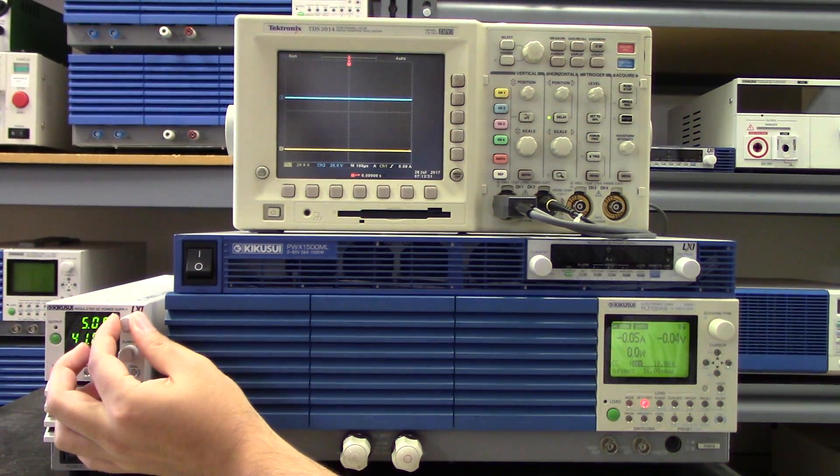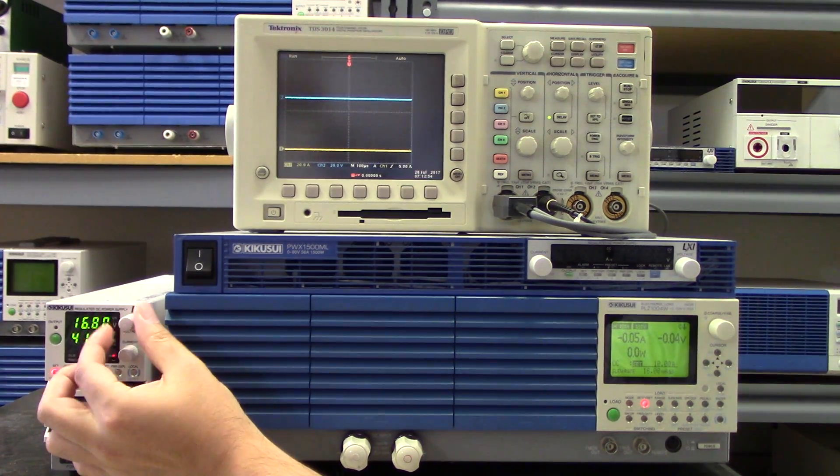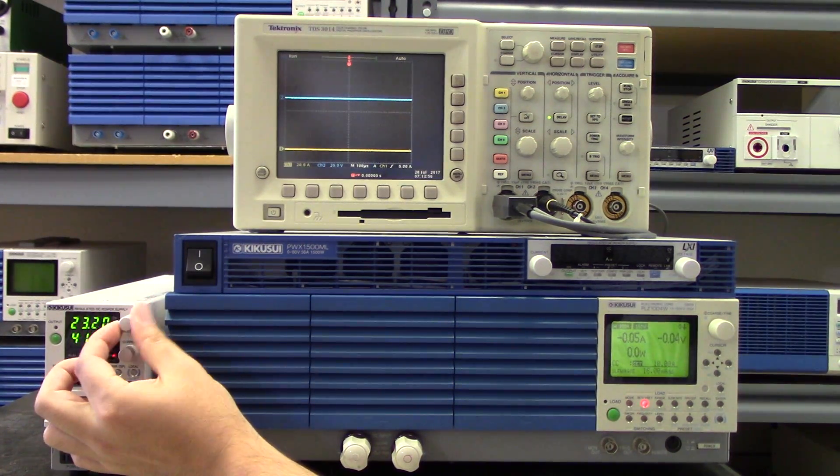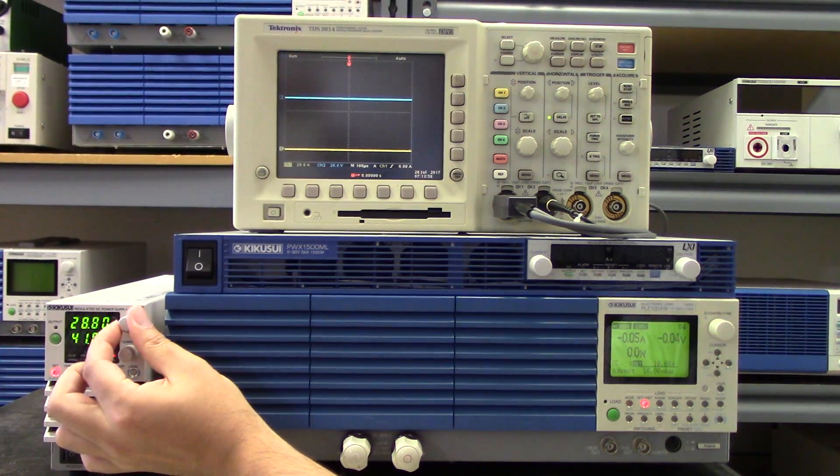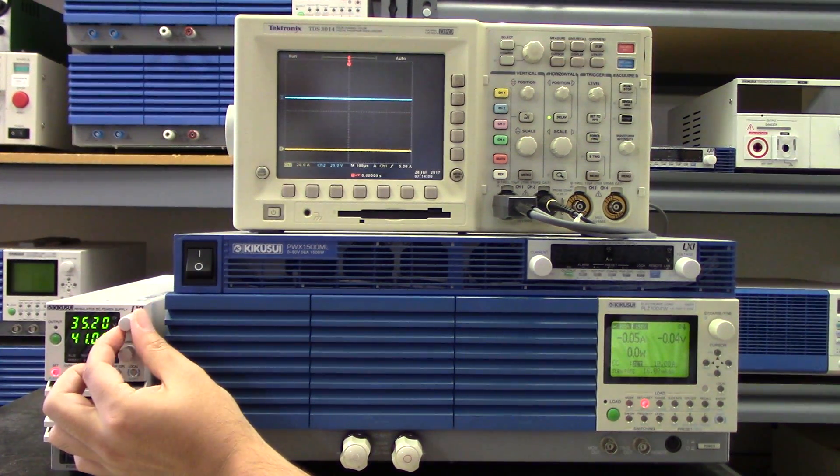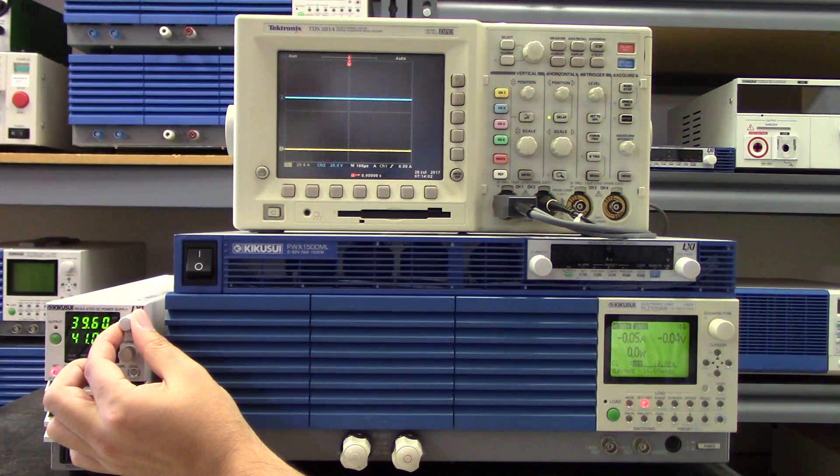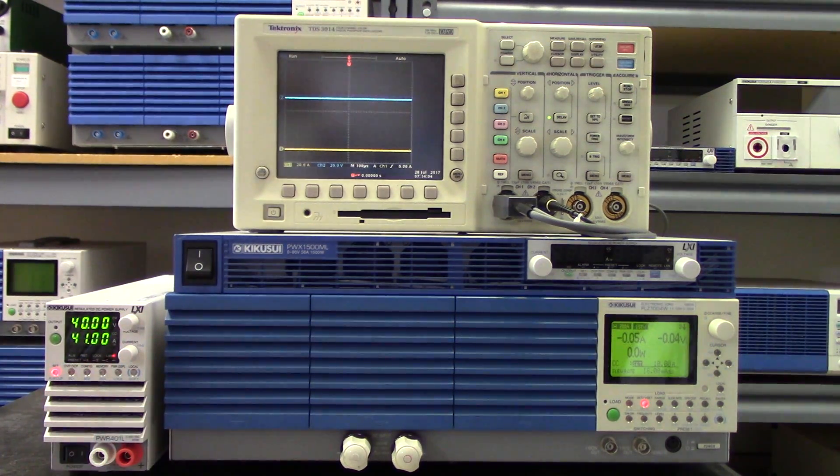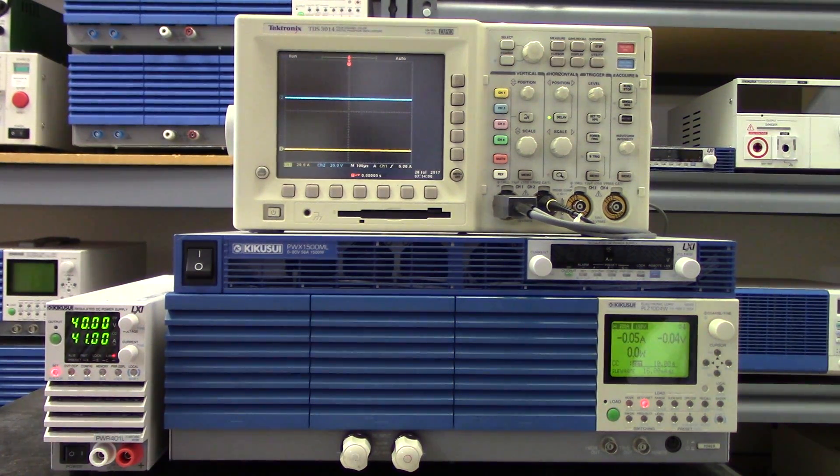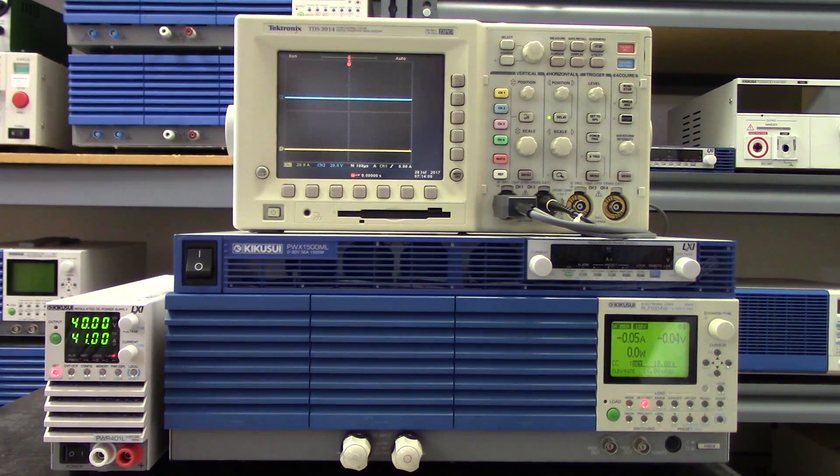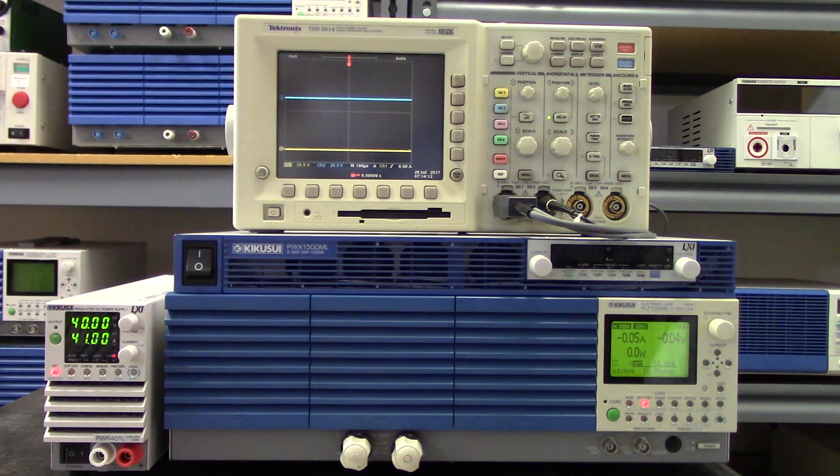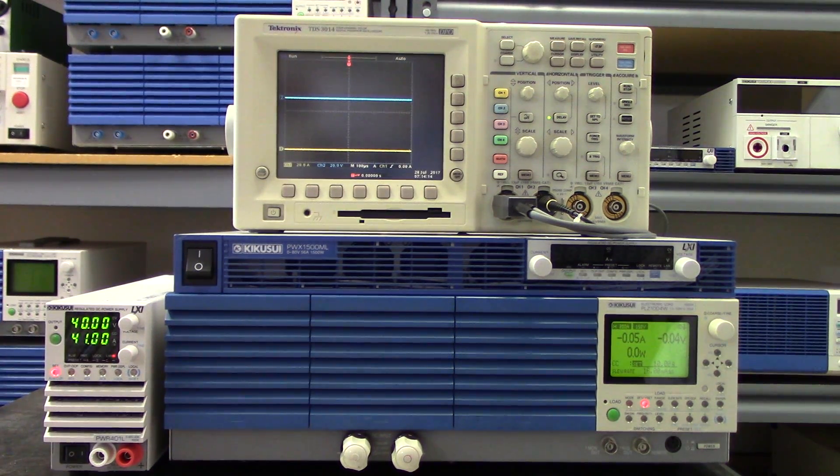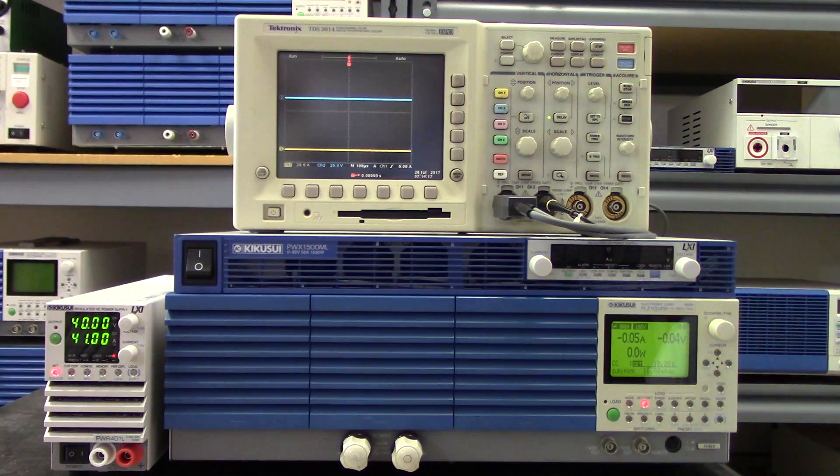So this is perfect for applications that require multiple voltages within a specific power range, and it really shines in automated testing and system integration where space in the rack is at a premium. Because with traditional DC benchtop supplies you would need multiple supplies to output 40 volts and 10 amps as well as 10 volts and 40 amps, but with the PWR-01 you can do both and anything in between in one unit.